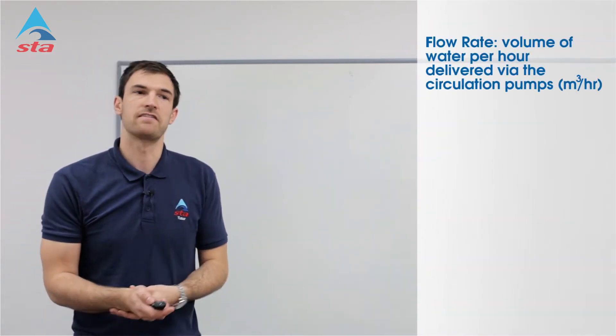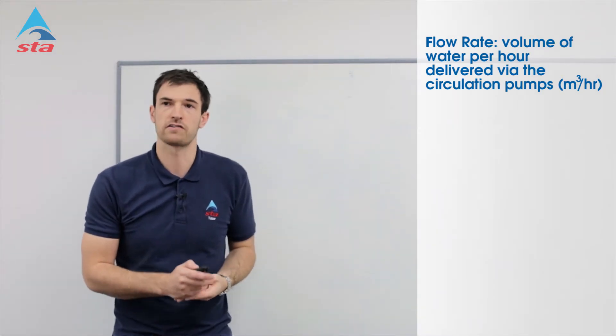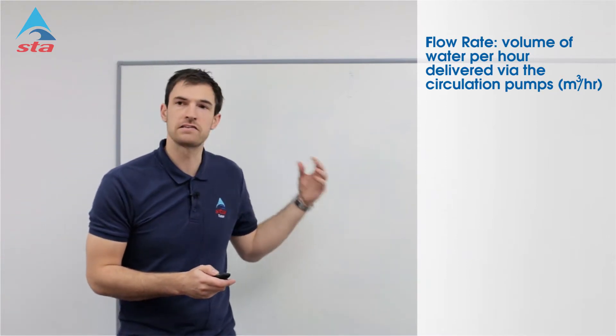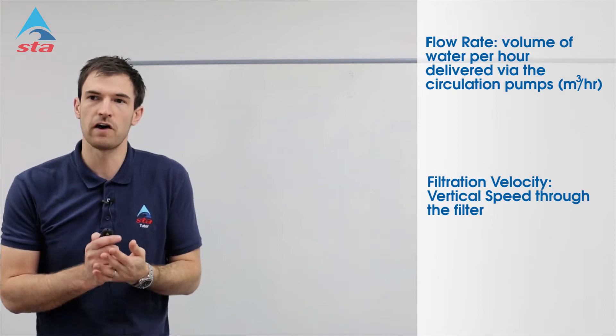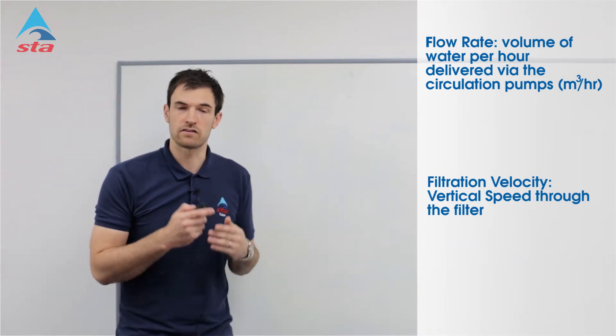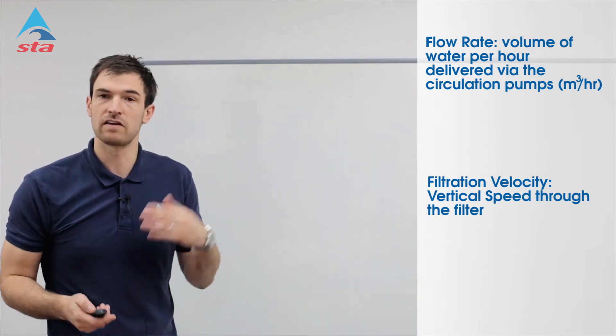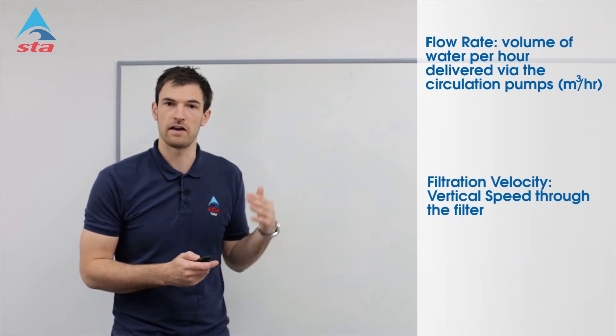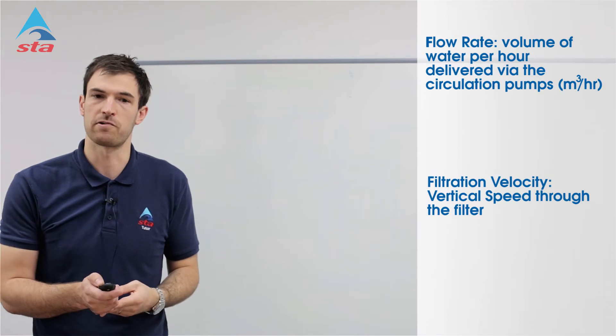Your flow rate is your volume of water per hour delivered via your circulation pumps. That's a measurement of volume, so that's going to come in metres cubed per hour. Your filtration velocity is the vertical speed through the filter — that's a speed, a time over a distance, so that's going to be metres per hour, which is also equivalent to a cubic metre per square metre per hour. Just bear that in mind as we go through the presentation.